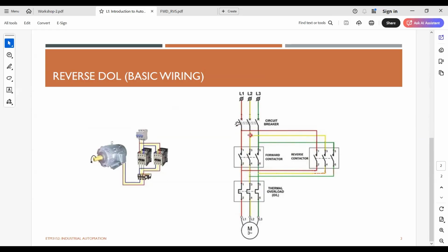But you can closely observe that the yellow one, the L2, comes here and it is swapped to L3 of the motor. And the green one, L3, comes here. It is changed to now the yellow color one, or the L2 terminal. So L2 and L3 are now reverse connected to the motor terminals, which results in the motor rotating in the opposite direction. So this is the basic wiring diagram.